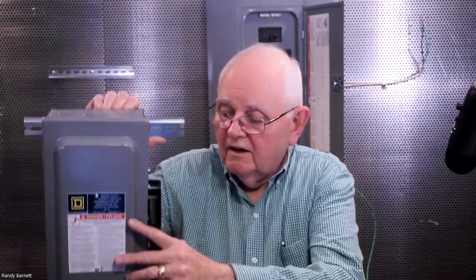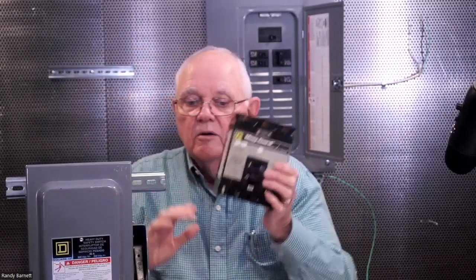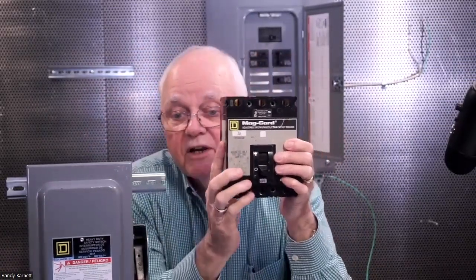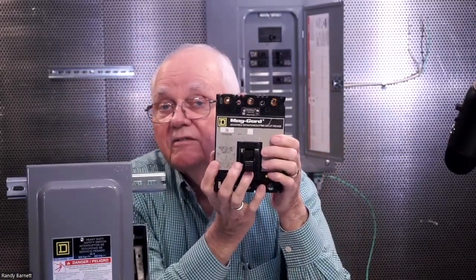So the general rule is I have to have an individual disconnecting means for the motor controller. Also, subsection B, which talks about the motor, then tells me I have to have a disconnecting means for the motor. So that's two disconnects, except really if I read through here, I find out I can kill two birds with one stone. I'm allowed to use one disconnecting means in certain applications for both the motor controller and the motor disconnect. I also find out that as far as location is concerned, what's important is that my equipment be within sight of this disconnecting means, whatever type it is, whether it's this safety switch once again, or a molded case circuit breaker, like this instantaneous breaker motor circuit protector, which can be located inside of an MCC bucket. In fact, that's where this one came from. I've got to be within sight of that. In other words, within 50 feet and visible. However, there are exceptions to that rule, and you want to read that.